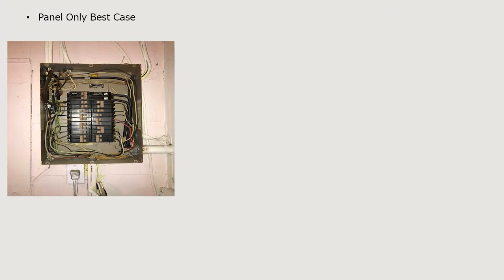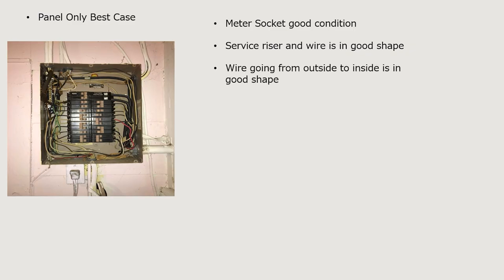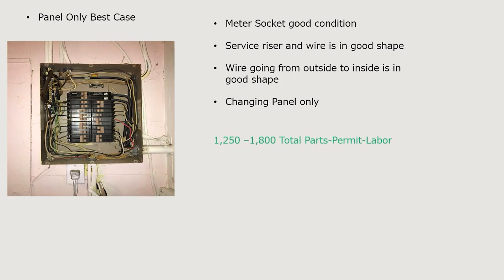Let's start with the panel change only — this is the best-case scenario. There are lots of different things that could change this price, so I give a very large range to accommodate for some of those. This assumes your meter socket outside is in good condition and I only have to replace the panel. It also assumes code doesn't require a disconnect, the riser wire is in good shape, and the wire going from outside to inside can be reused.